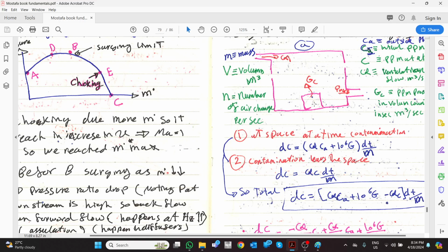But you will have an idea what flow is required. By the way, if it is dangerous gases, like diesel gases, it needs to be from 20 to 25 air exchanges, and sometimes 30 exchanges, like if you have ozone, etc. So how will we do this calculation?